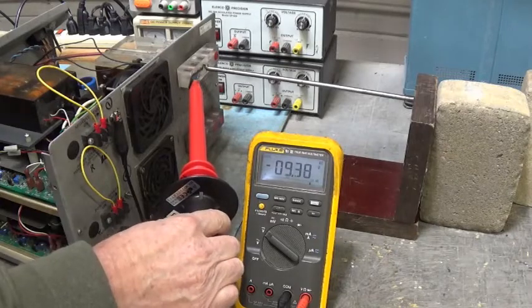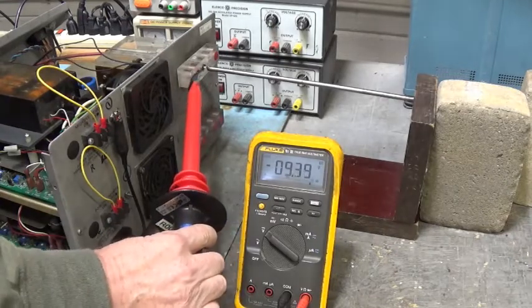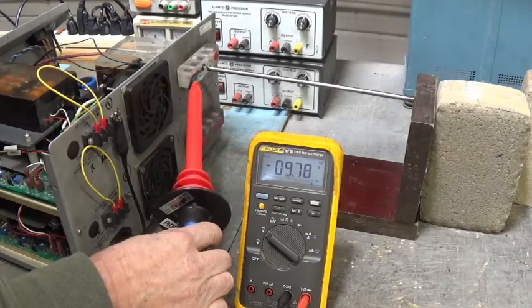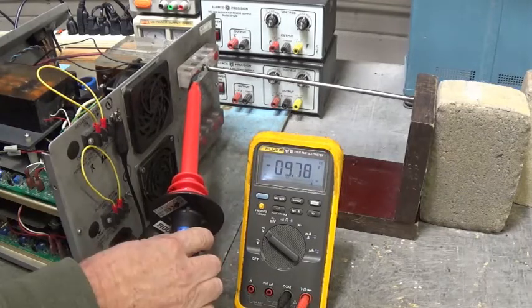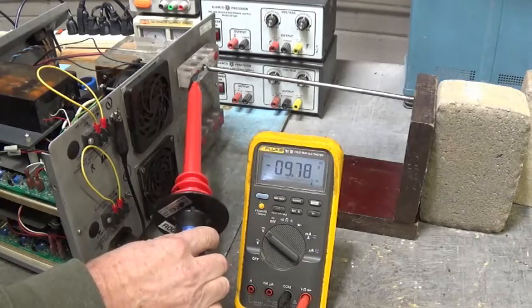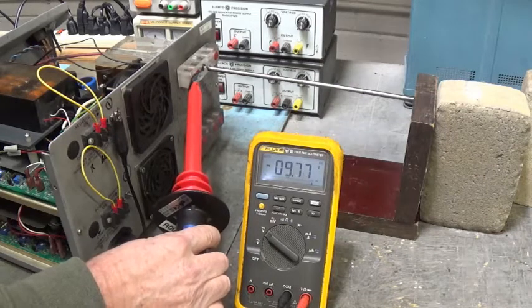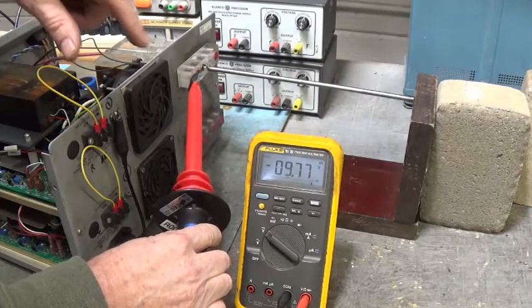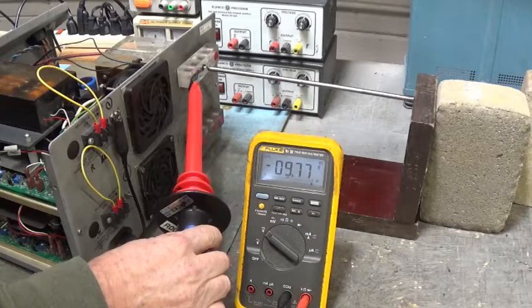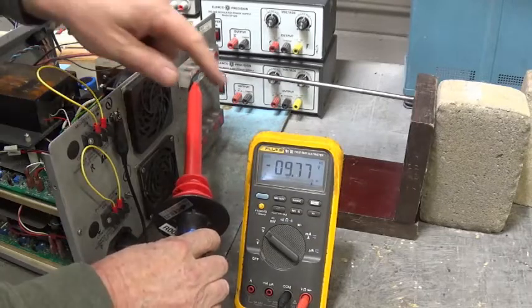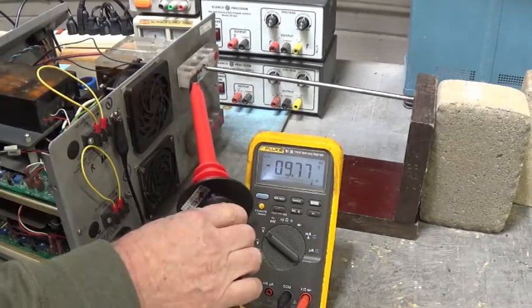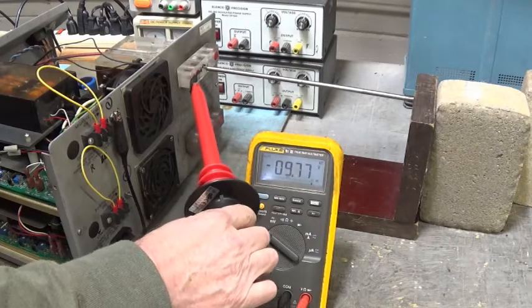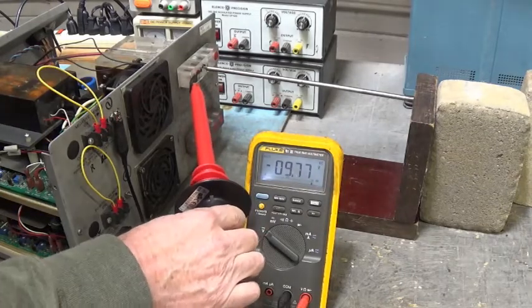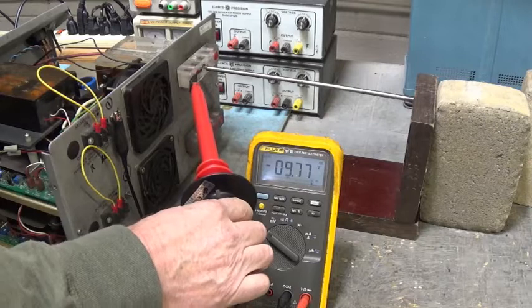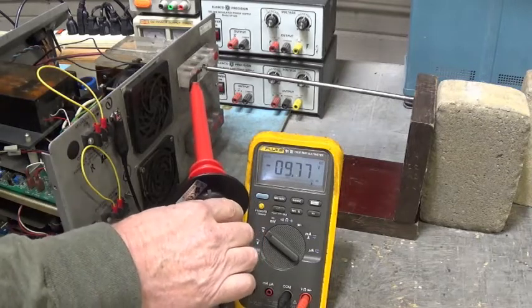There we go, that's good contact right there. There's 10,000 volts on the meter. We're a little bit low, but I'll show you how to make that adjustment to bring it up. We have negative 9.77 volts DC on the meter, indicating we have 9,770 volts at the output, right there at that metal rod.